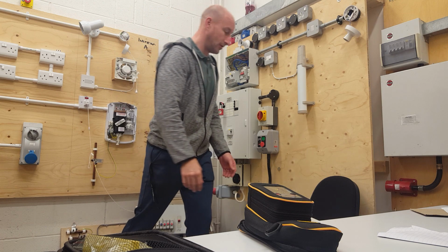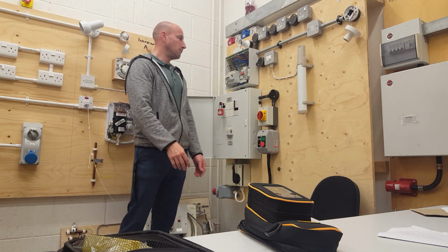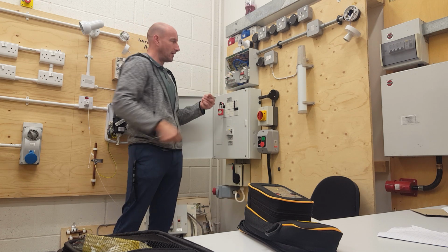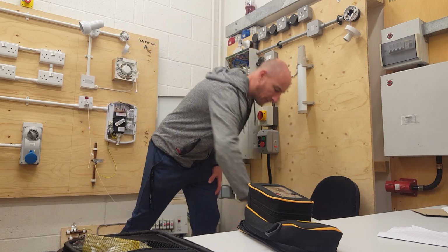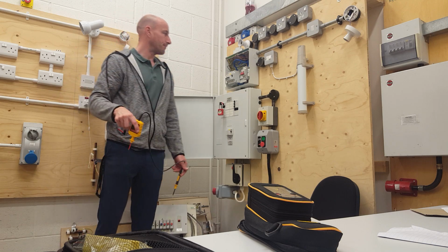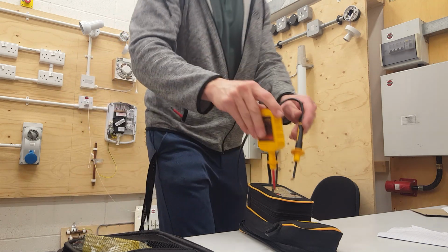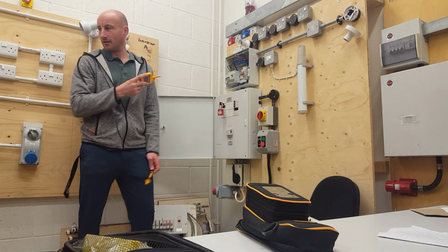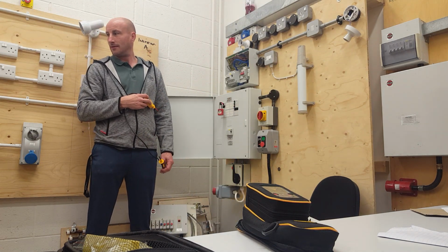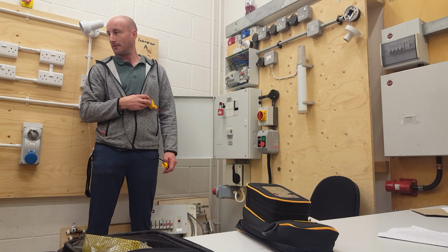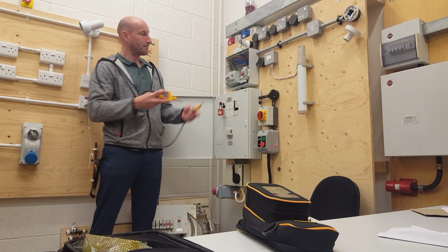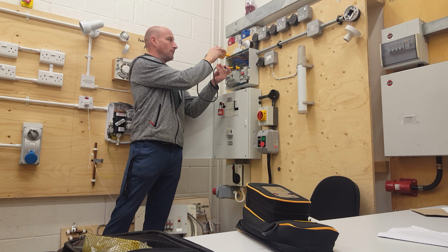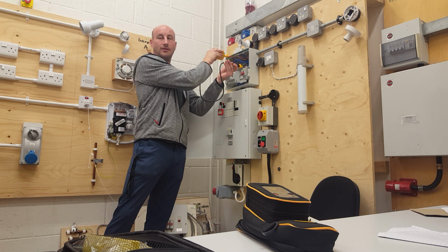So what we're going to do first, incoming towards the top of that. Maybe not always, but you can see the cables coming out, you can see the cable coming to there from there. So what we're going to do first is test the tester, make sure it works. How many tests are involved in this? Just 3, isn't it? What's the 3 tests? Live to neutral, live to earth, and neutral to earth. That's it, there's only 3 tests.